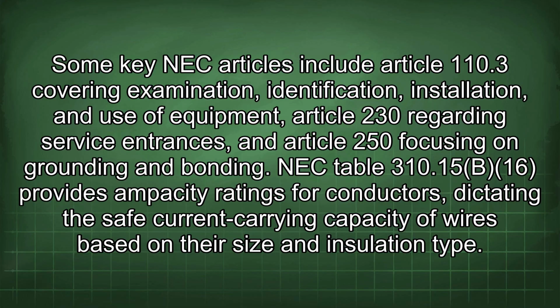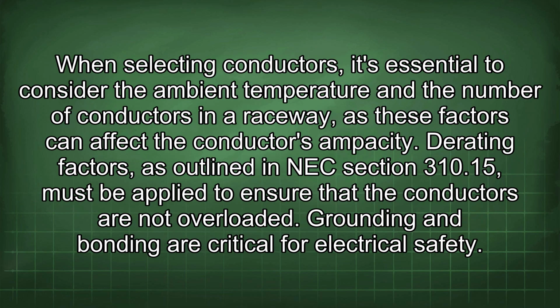NEC Table 310.15(B)(16) provides ampacity ratings for conductors, dictating the safe current carrying capacity of wires based on their size and insulation type. When selecting conductors, it's essential to consider the ambient temperature and the number of conductors in a raceway, as these factors can affect the conductor's ampacity. Derating factors, as outlined in NEC Section 310.15, must be applied to ensure that the conductors are not overloaded.